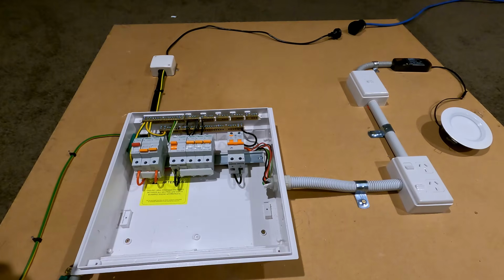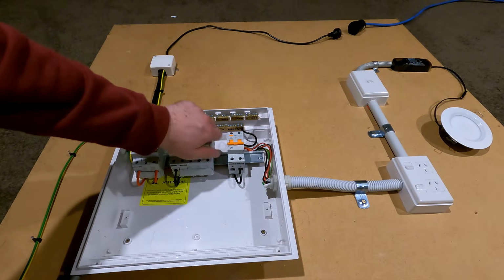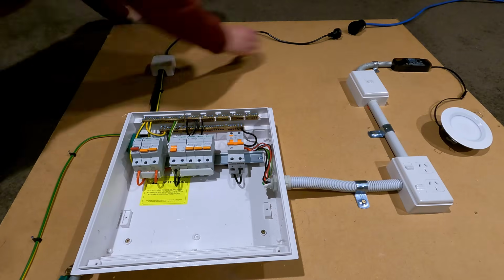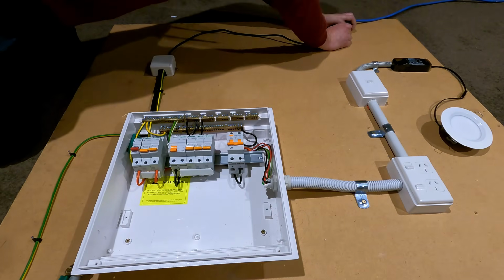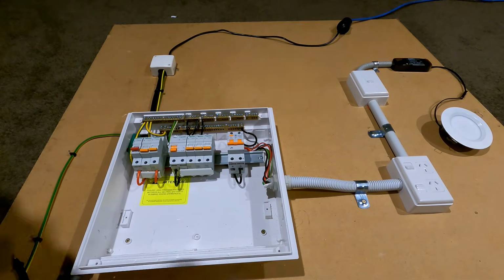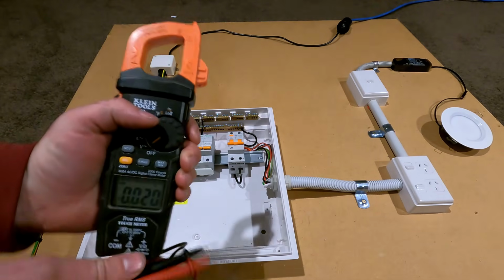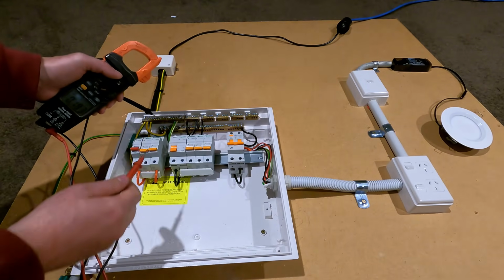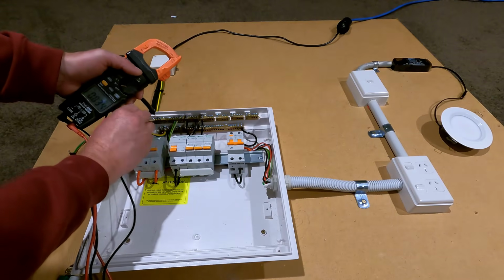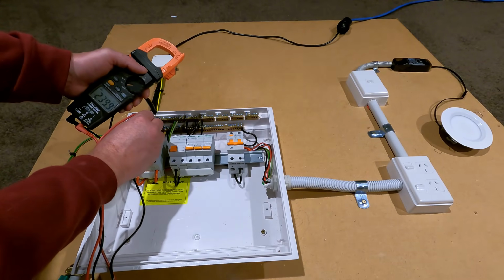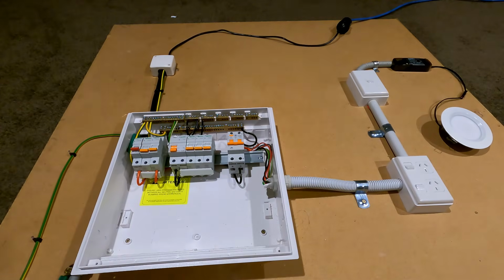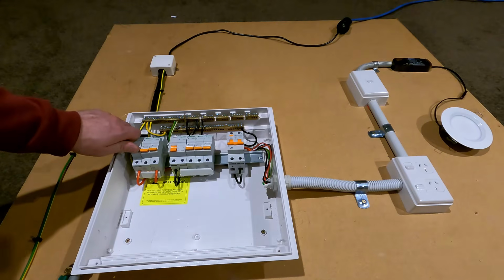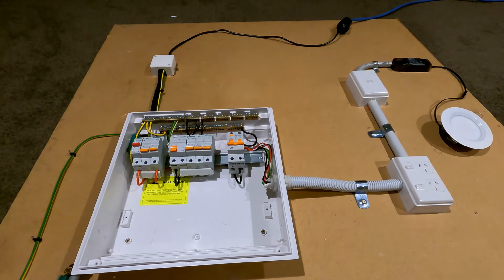So before we plug her in, what we'll do, make sure everything's turned off. Now that it's plugged in, we'll verify that we've got 230 volts there. So earth to line side, we've got our 230, 240 volts. So now that we're happy, we've done our continuity checks, we know the phases go to the top of the RCDs, we know the neutrals are in place, we've done all our other tests, so we can, by all means, liven these circuits.